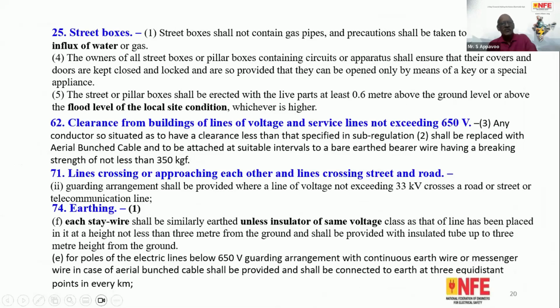So apart from that, street boxes, because during the rainy season and other times, there are a lot of places where people can become victims. So the regulation insists the pillar boxes should be provided above ground level, with clearance from the building. So these are the provisions that I have given earlier. And earthing is an important thing. The stay wire should be earthed, and the guarding arrangement should be provided along the street and it should be earthed.